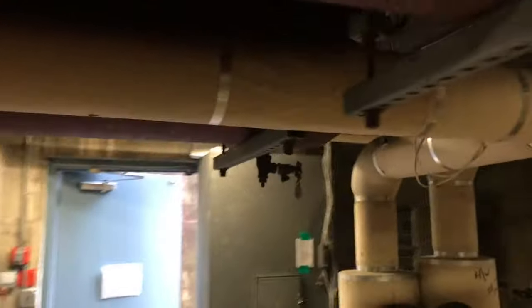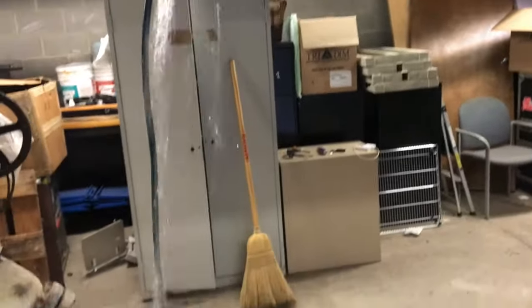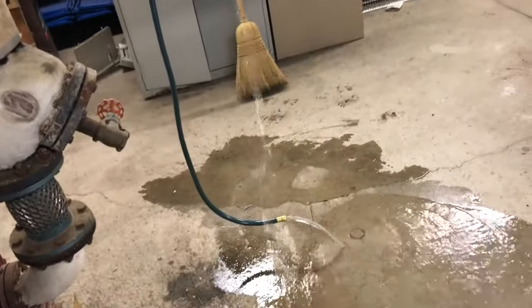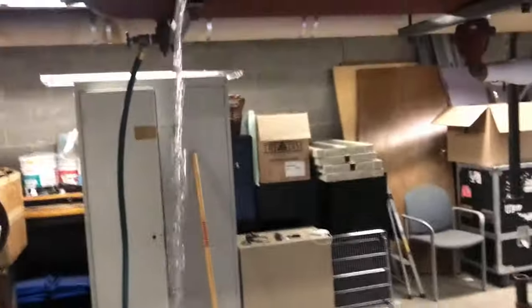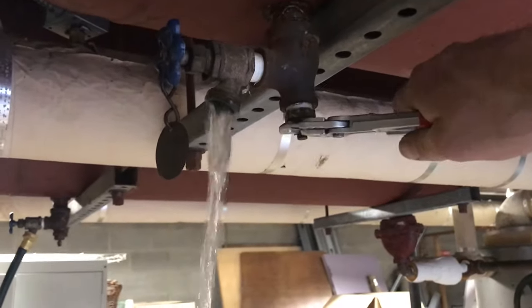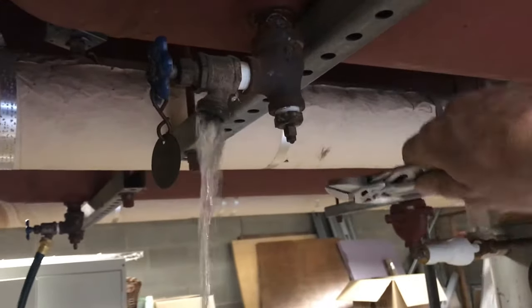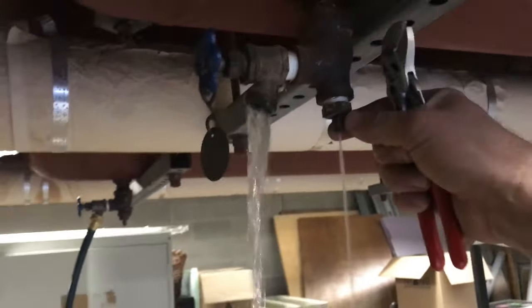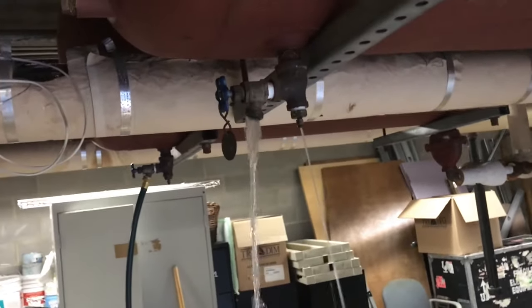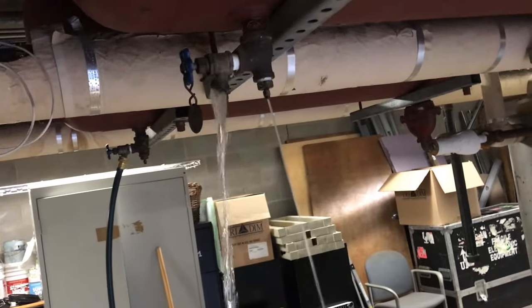Now let's go to the other tank. I don't have a hose on here but this water should go to the floor. I'm going to slow it down a little so the splashing is not all over the place. Let's open the air — and we got water coming out. So this tank is waterlogged. We're going to let this one drain down.